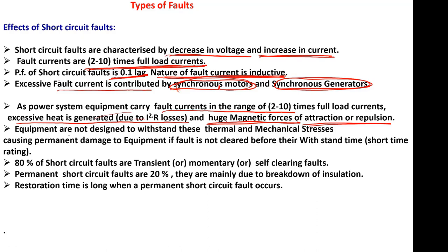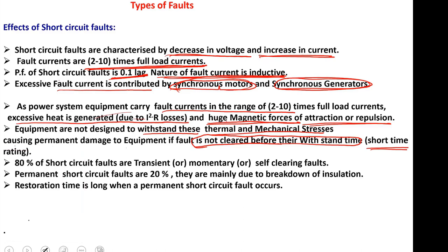The equipment is not designed to withstand these thermal and mechanical stresses, causing permanent damage if the fault is not cleared before the withstand time of the equipment. Every equipment has some short time rating — the amount of time for which it can carry the fault current without getting damaged.